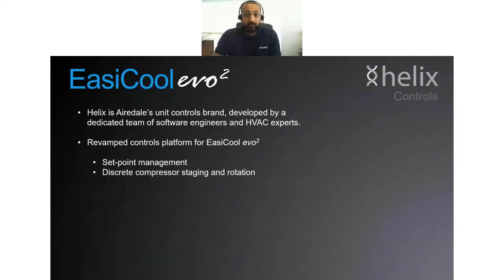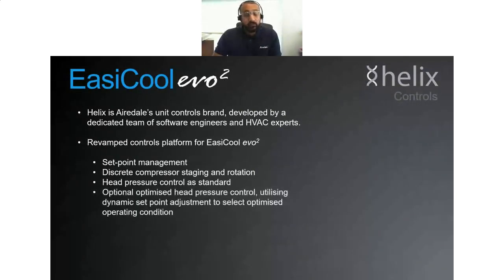We can alter the return air set point and the supply set point via the controller. Discrete compressor staging and rotation is possible. Head pressure control is standard. We also have an optimized head pressure control option utilizing dynamic set point, adjusting to the selected optimized operating condition.